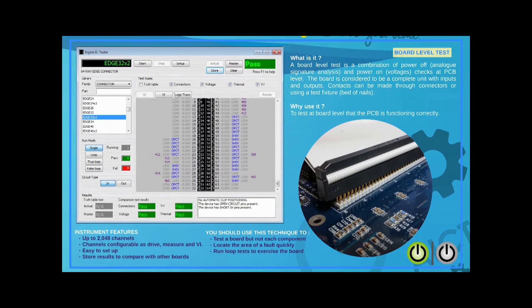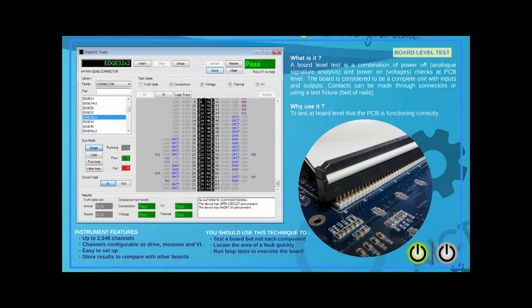From the edge connector, users can drive logic signals, read voltages, generate VI signatures, and save connection information. If a bed of nails is available, the test results can be collected from multiple test points at the same time.